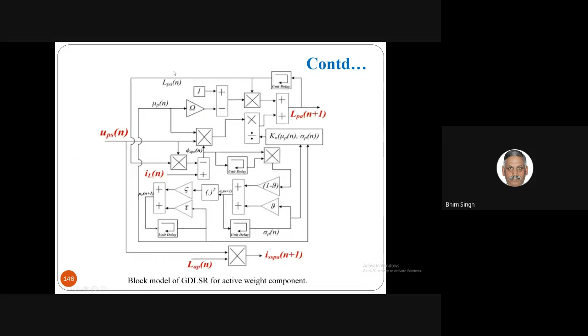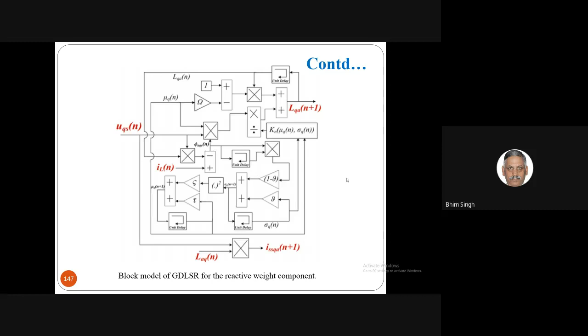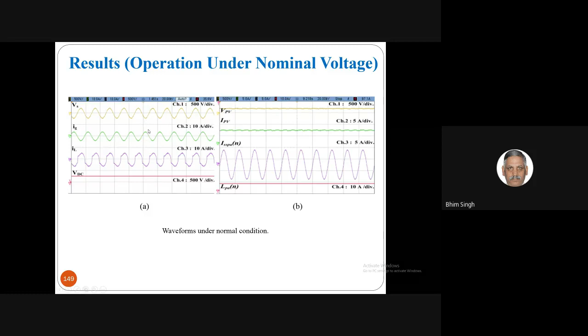Even if the grid is bad, we should still be able to feed the power to the grid and maintain unity power factor, with the current in phase with the voltage, and meet the requirement of local loads. That's typically the control. You can see clearly that voltage and current are out of phase, so power is fed to the grid, but the compensation of the non-linear load current is taken care of by the inverter. So the grid side reflects only active power at unity power factor, and meeting the local requirement of the load is taken care of by the inverter.